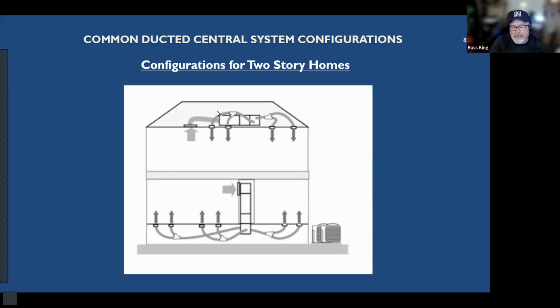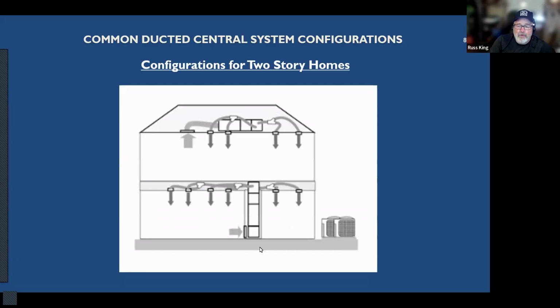Okay. The upstairs is probably going to be a horizontal unit serving the upstairs, and then the downstairs, it depends on how much room you've got. If you have a crawl space, you can do ducts in the crawl space like that. Okay. That's fairly common. If you don't have a crawl space, if you have a slab on grade house, you can have an upflow on the first floor and a horizontal on the second floor. That's fairly common. Now, the hard part is getting these ducts through the floor joists.